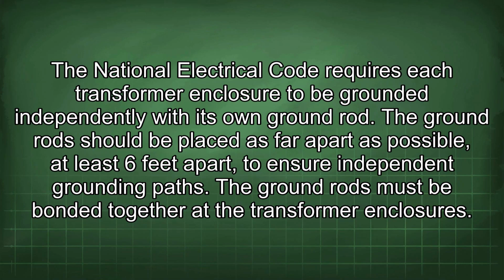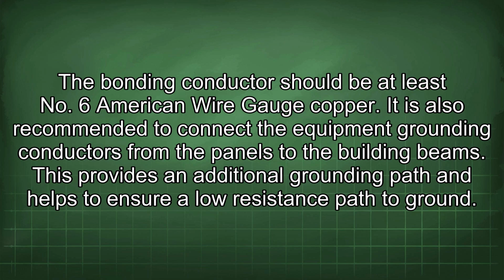The National Electrical Code requires each transformer enclosure to be grounded independently with its own ground rod. The ground rods should be placed as far apart as possible, at least 6 feet apart, to ensure independent grounding paths. The ground rods must be bonded together at the transformer enclosures. The bonding conductor should be at least 6 American wire gauge copper.